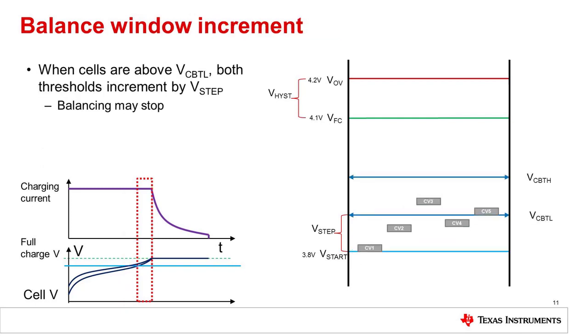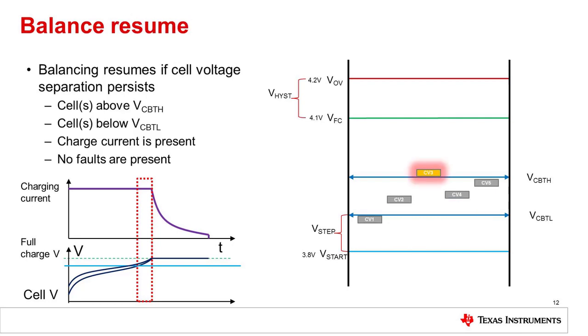When all the cells are above the lower threshold, both thresholds will increment by a value of V-step. In this example, balancing will stop since there are no longer cells above the high and below the low threshold. At this point, the charge current is still high, and as the cells rise once again, since there are cells above and below the two thresholds, balancing resumes on those above the high threshold.